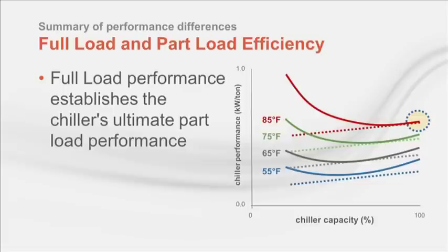This begs the question, how can the return on investment be maximized and the payback period be minimized? Mick and Brian will discuss this more in a moment, but an interesting result of an analysis that includes real utility consumption and demand charges reveals that the plant efficiency, and importantly for this discussion, the plant financial ROI can be significantly improved by investing in a variable speed chiller that includes premium full load efficiency.